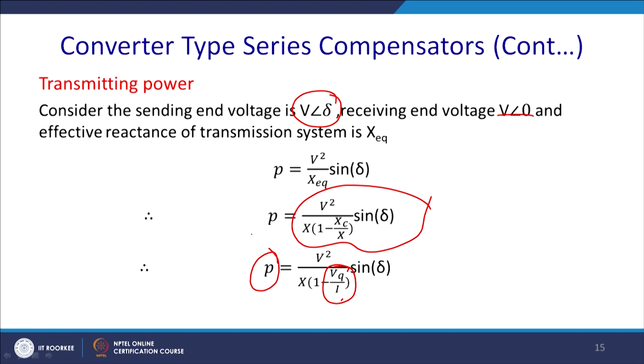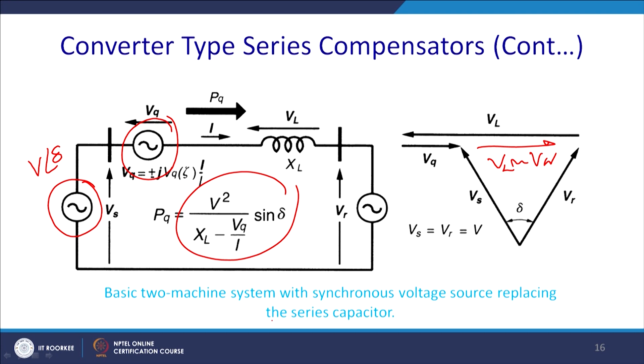So, this is the converter type series compensation circuit diagram. You have a similar two machine model. You have a sending end voltage V angle delta. Thereafter you can assume that you have placed a series compensator VQ as a voltage source added in series. This series compensator will have a property of plus or minus j VQ times I by mod I, that is the unit vector, and thus the real power transmitted in this case is V square by XL minus VQ by I sin delta, and ultimately this will be the phasor. Effectively this voltage becomes VL minus VQ. So, this is a basic two machine system of the synchronous voltage source replacing a series capacitor. So, you can have the same control with a voltage source instead of actually reducing the value of the impedance.